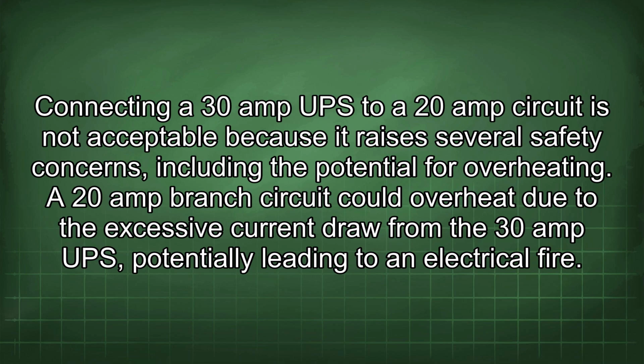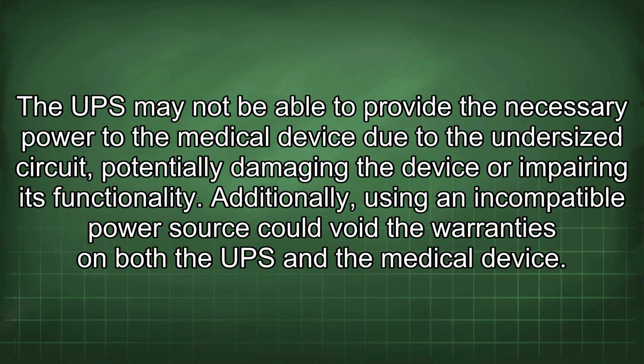A 20 amp branch circuit could overheat due to the excessive current draw from the 30 amp UPS, potentially leading to an electrical fire. The UPS may not be able to provide the necessary power to the medical device due to the undersized circuit, potentially damaging the device or impairing its functionality. Additionally, using an incompatible power source could void the warranties on both the UPS and the medical device.